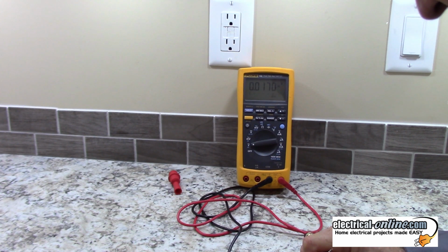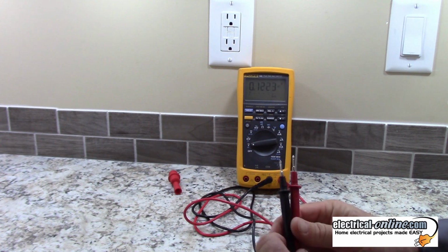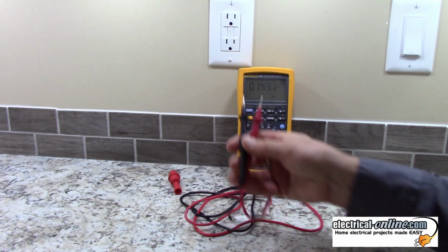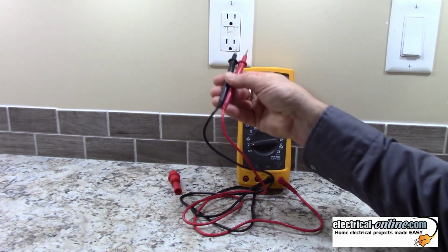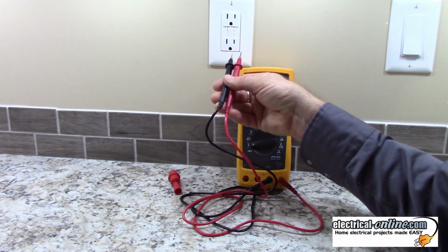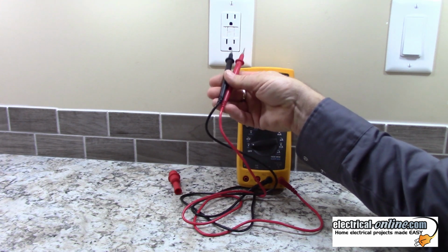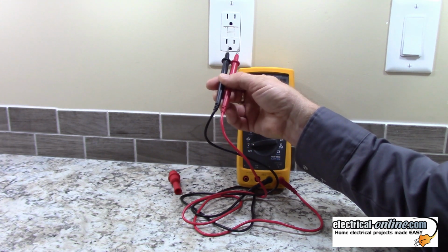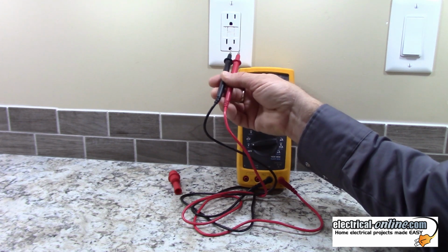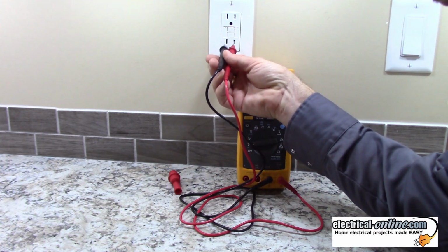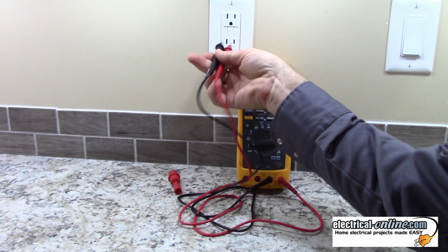I'll just touch those leads together to make sure we got as close to 0 volts as you can get. So now we'll try hot to neutral, and we should expect about 120 volts. Now this is a tamper resistant outlet, and the functionality of those says that you have to be plugging in a plug with 2 prongs or 3, but you have to have the 2 prongs plugged in and push them in at the same time or they're not going to go in.